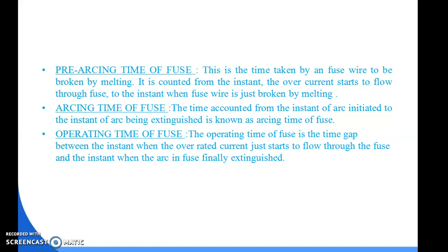Pre-arcing time of fuse. What is this pre-arcing time? This is the time taken by a fuse wire to be broken by melting. It is counted from the instant the overcurrent starts to flow through the fuse to the instant when the fuse wire is just broken. That is called the pre-arcing time of fuse. What is the arcing time of fuse? The time counted from the instant the arc is initiated to the instant the arc is extinguished is known as the arcing time of fuse.